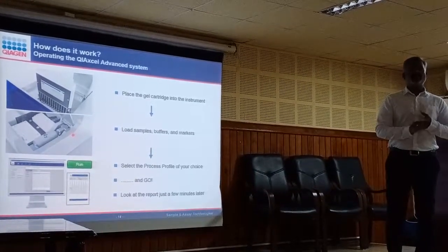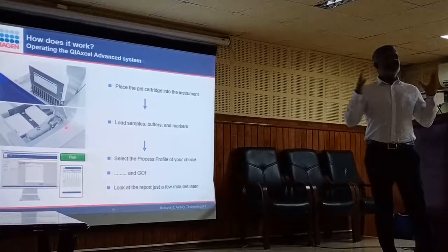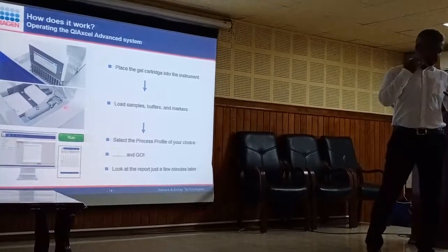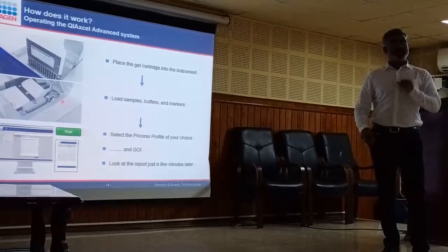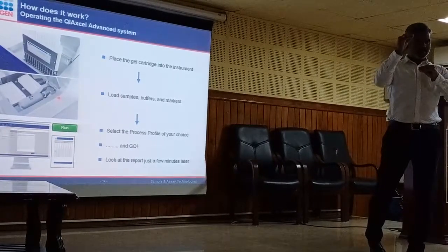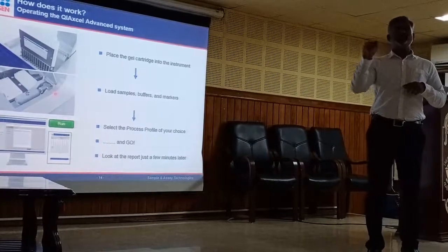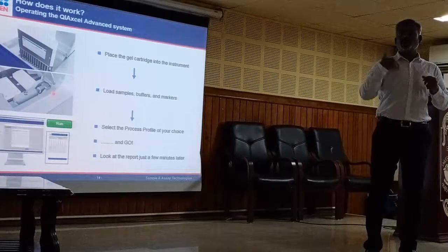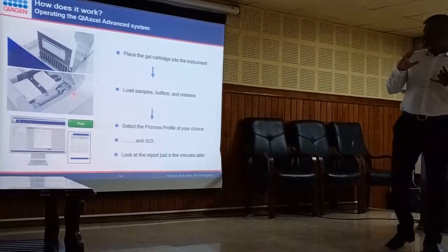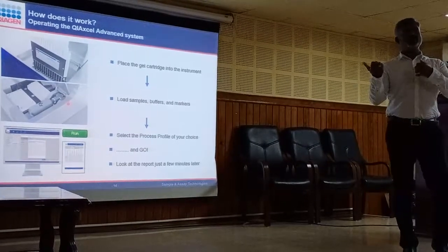There is a peak-calling option: if you are working on 5 different pathogens across 1,000 samples, you call the peaks — Peak A for pathogen A, Peak B for pathogen B — and after analysis the machine reports which well contains which pathogens. This is called peak calling, and your report comes ready for you to track which sample has which pathogen. Data export and import is flexible — you can export to Excel format and import sample information in Excel format as well.